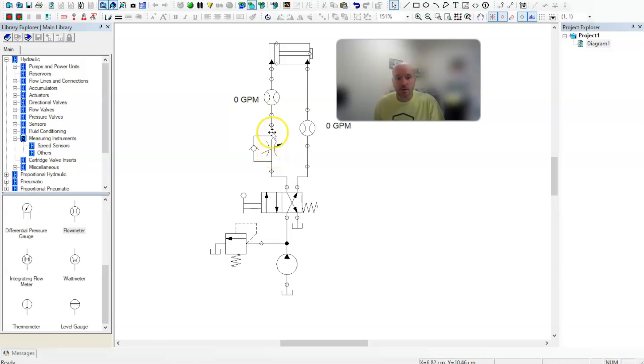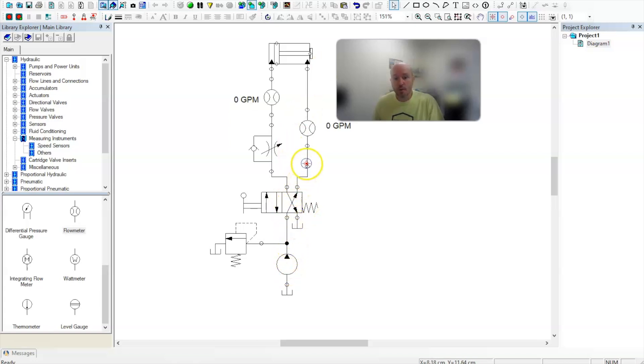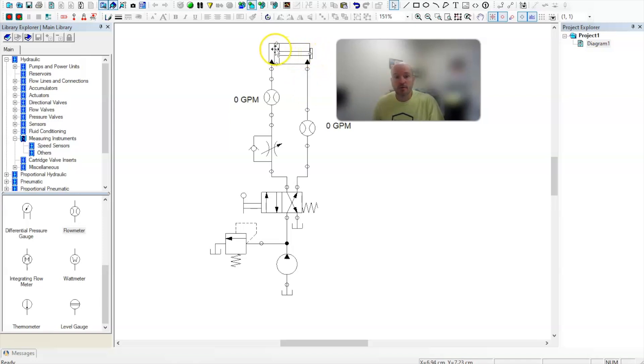As oil flows up, it will go through here extending the cylinder at whatever speed I set it to. Then when I come back to its original position, oil will flow through here into the cylinder's B port. Oil will free flow through here and all the oil will exit this cylinder out through the bypass check valve.